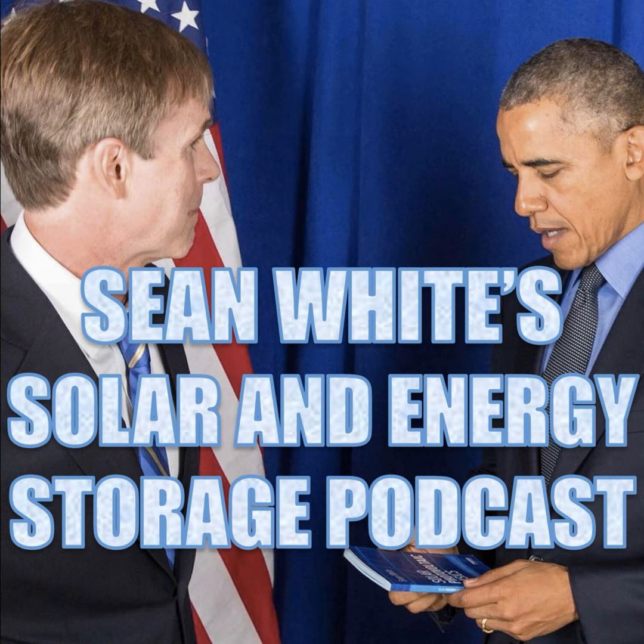Electrolyte containment. You've got to look out for spills of electrolyte, and it says an alarm system shall be provided to signal an electrolyte leak from the system. And also your wiring should be routed in a way that mitigates potential for exposure of your wires to these electrolytes. So yeah, you don't want to dip your wires in electrolytes. Not a good thing. Flow controls. So we're pumping electrolytes. We have pumps. It's a battery with pumps. Controls shall be provided to safely shut down the system in the event of electrolyte blockage. So if there's something that's getting blocked up, you need to turn those pumps off.